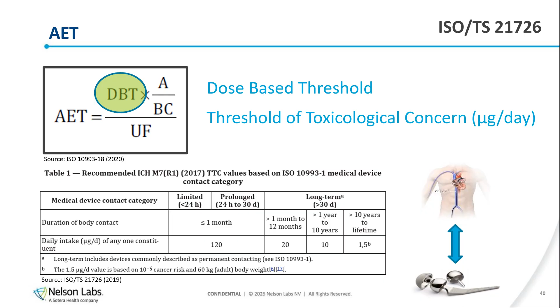Next up is the uncertainty factor. The uncertainty factor is there to account for the analytical uncertainty of the screening methods, because there is an inherent degree of uncertainty that you will have in the found concentrations of these methods. So any other method that is not a screening method or an organic screening method, the AET is not applicable.